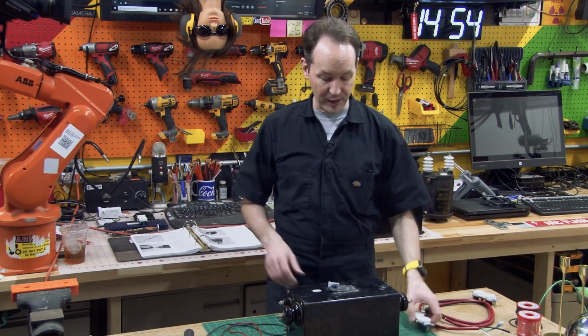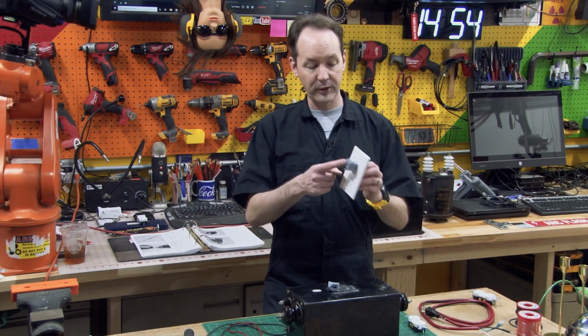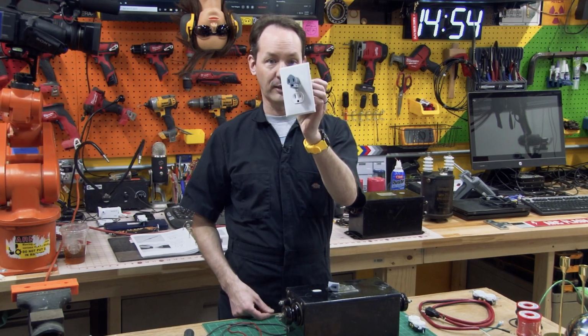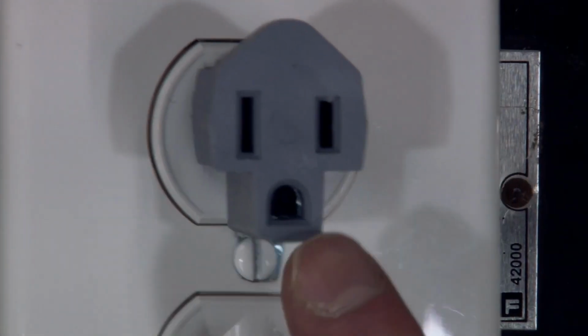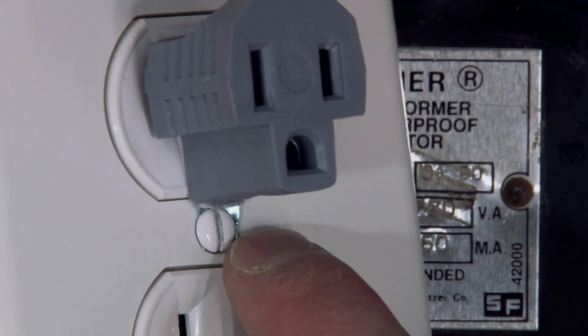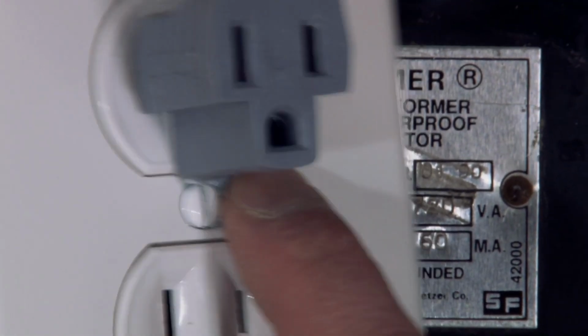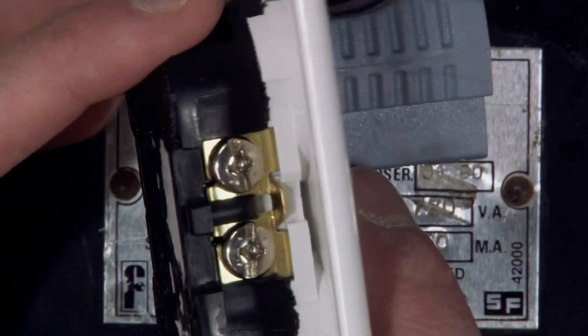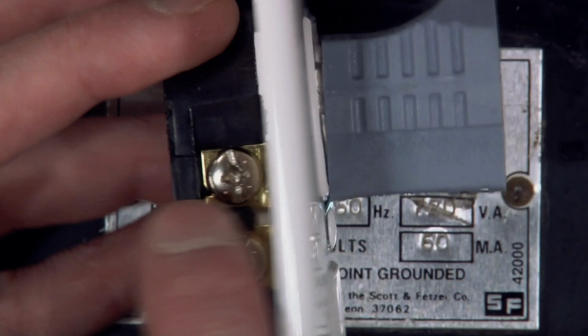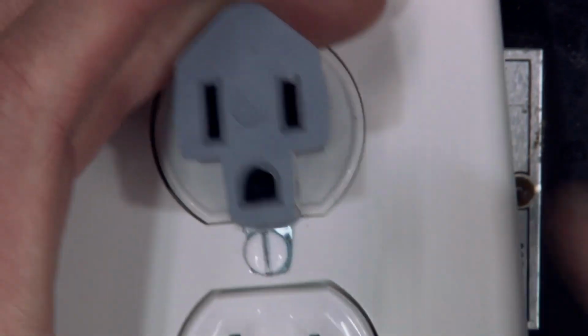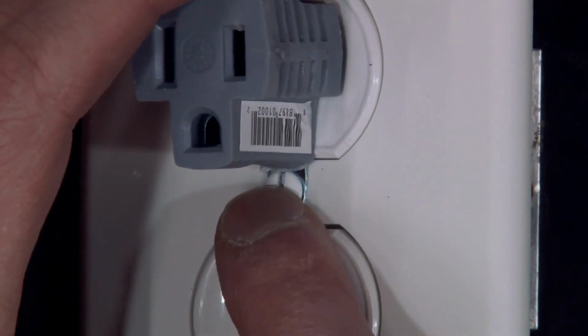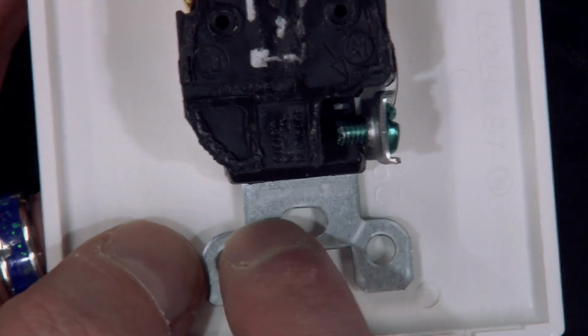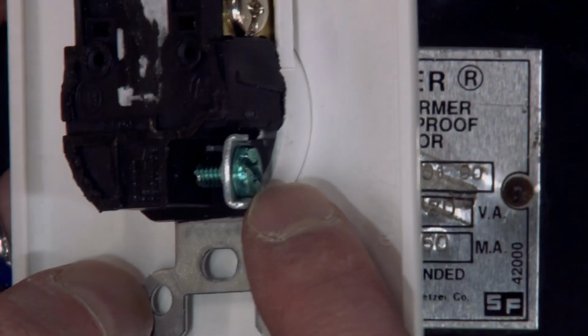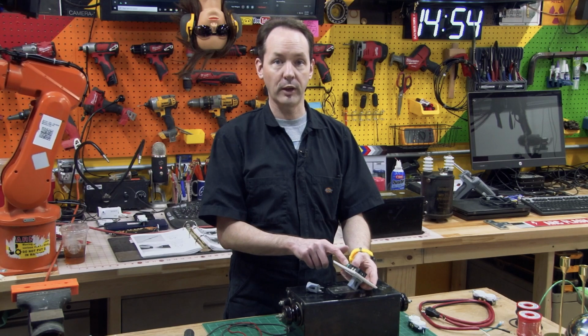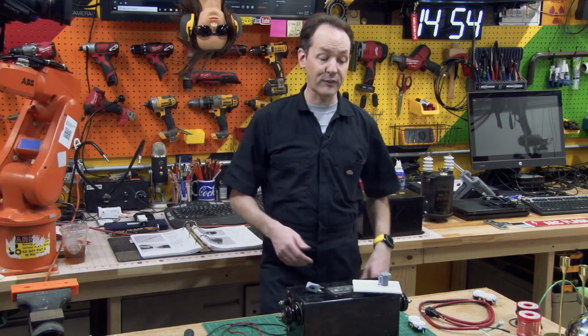So if you take that outlet and plug this in, look, there's one installed in a real outlet, okay? If you have this installed, the way this works is it connects ground to the screw, right? And the screw connects on the back. These are your neutral side, because they're white, they connect to the neutral, the big hole. These are your hot side, they're brass, they connect to the little hole. But what connects to that screw? Well, that's easy. That connects to the frame of the outlet, which connects to chassis ground, the green wire in your house. No problem, everything's fine.